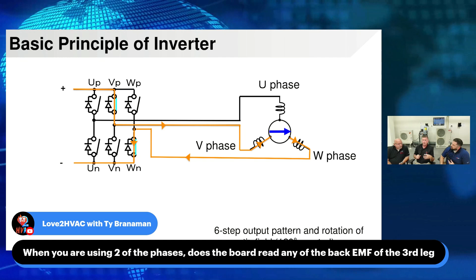Check for that balanced voltage, and then when you do find imbalanced voltage, we don't just replace the board and move on. We've got to make sure we figure out what happened. What caused that issue to begin with? Why was it unbalanced? It would have been a chain reaction. Exactly. Well, I know in my area, we have a lot of dirty power. We have a lot of very long power runs, especially in the rural areas, that get very low voltage. Frequencies can get off a little bit. And so I personally recommend using a good three-phase monitor and conditioner, or a single-phase monitor and conditioner, coming in to my outdoor unit, just to help clean that up.